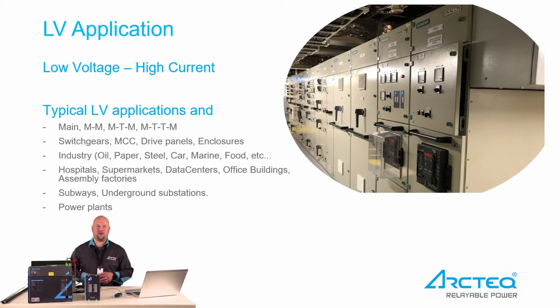A few low voltage applications. Again, low voltage, high current. Typical applications: main, which is one main incomer breaker. Main-main means one bus bar but two incomer breakers. Main-tie-main is the same, but with the tie breaker in between. And main-tie-tie-main means there are two main breakers, a tie breaker, a bus bar, and another tie breaker.